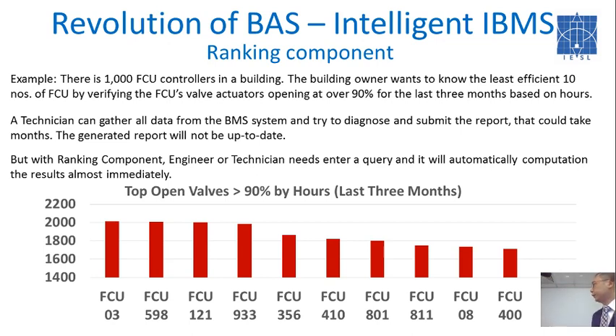Top open valve greater than 90% by hours, over the last 3 months. FCU number 3 opens more than 2,000 hours, so you're wasting a lot of energy. You will know that your fan coil is wasting a lot of energy based on these reports itself.